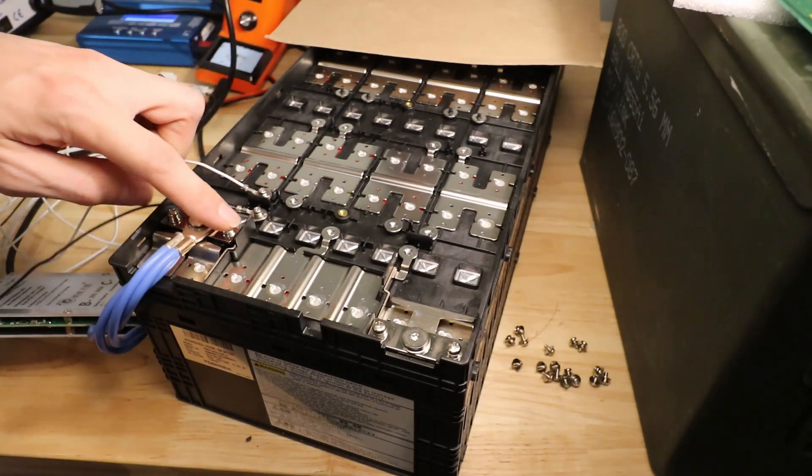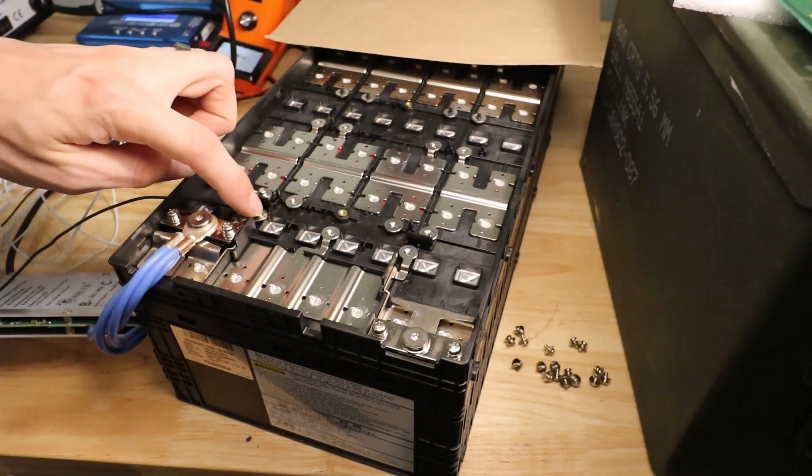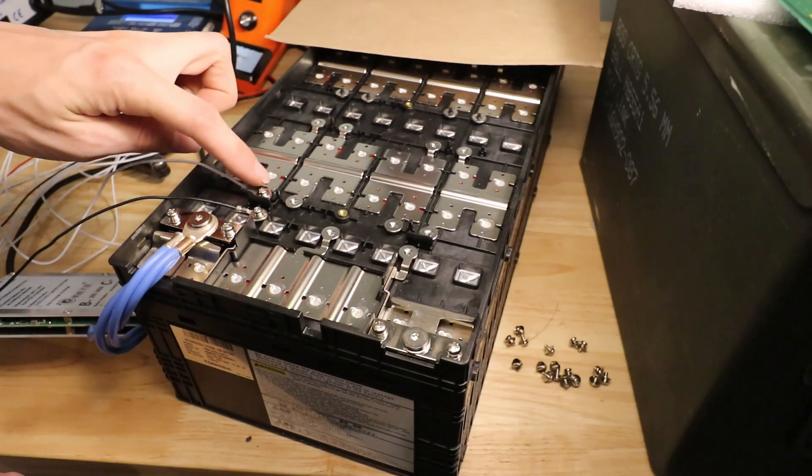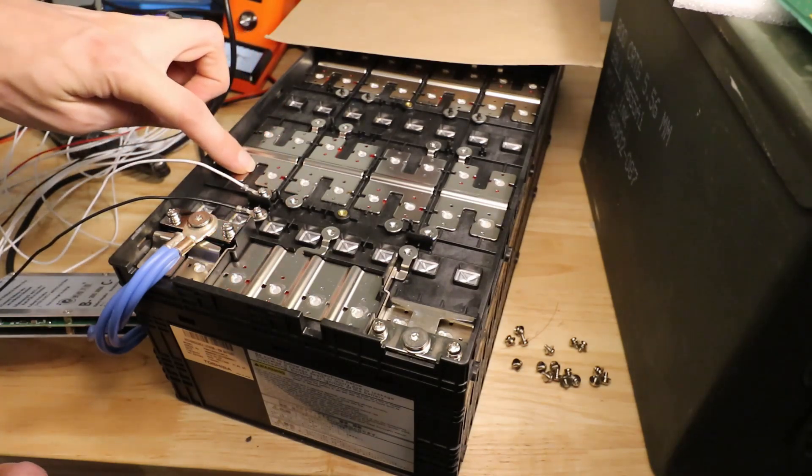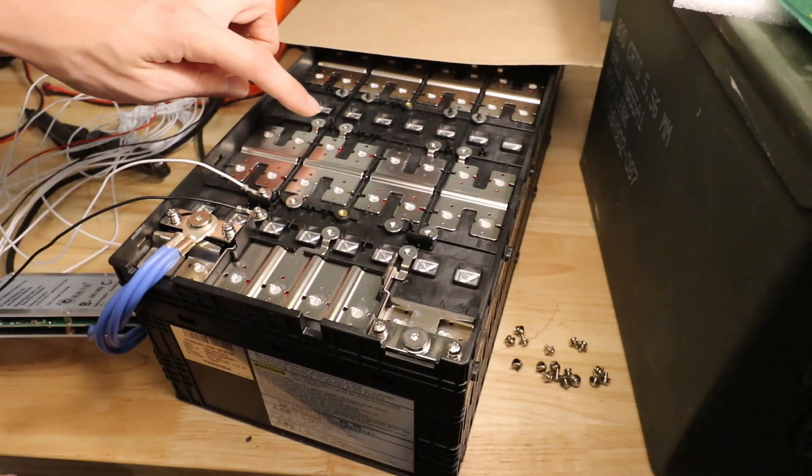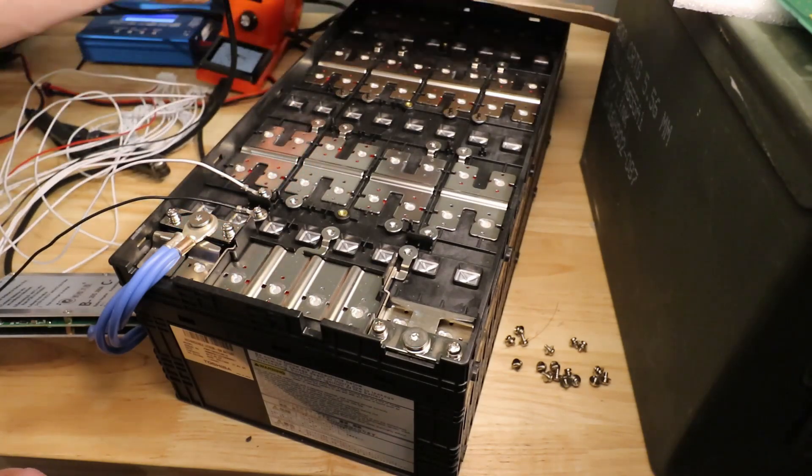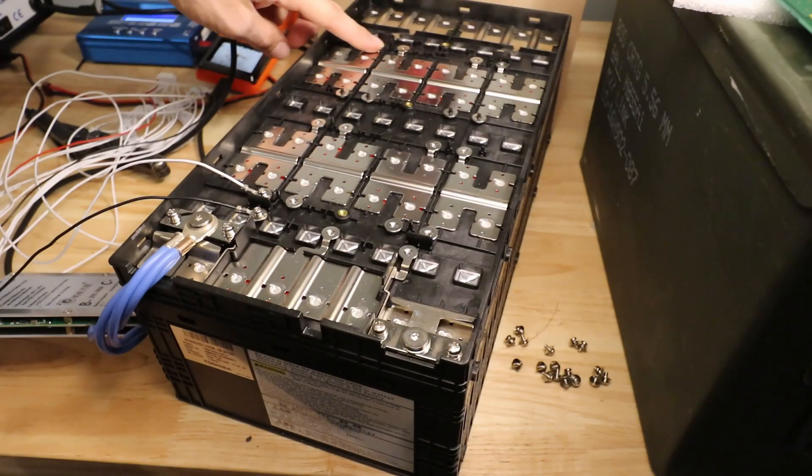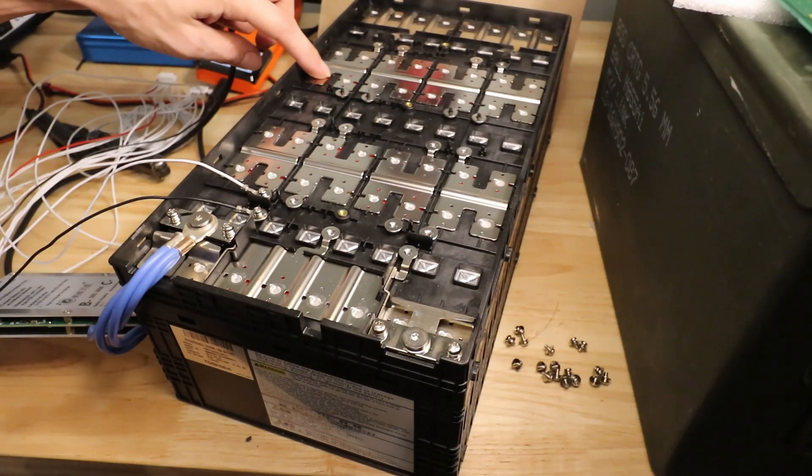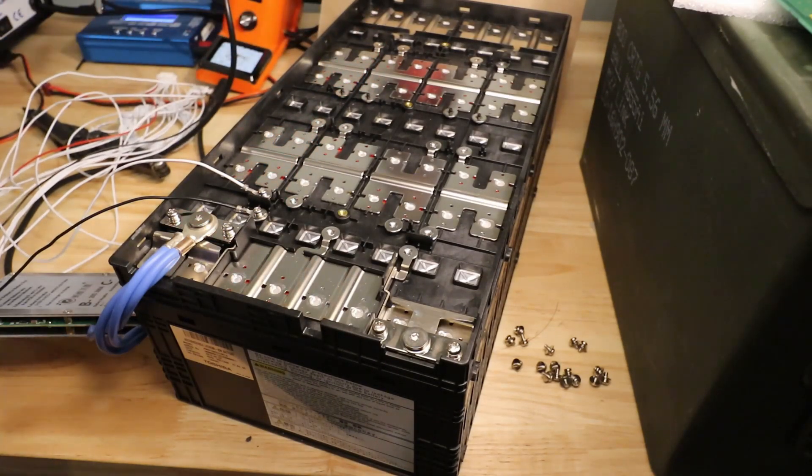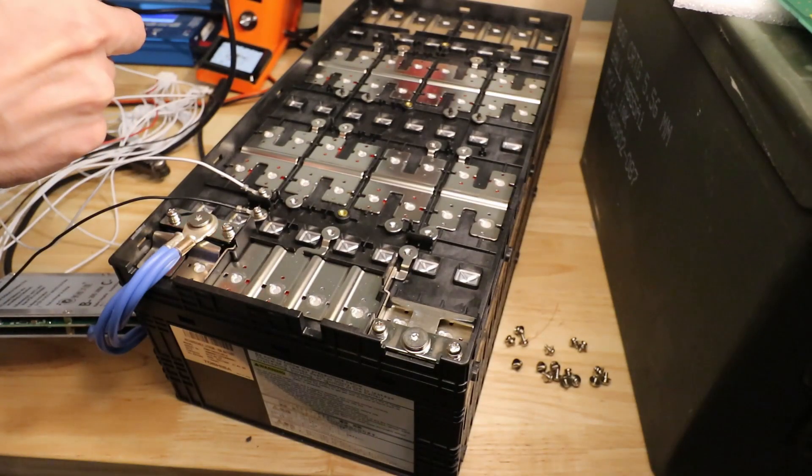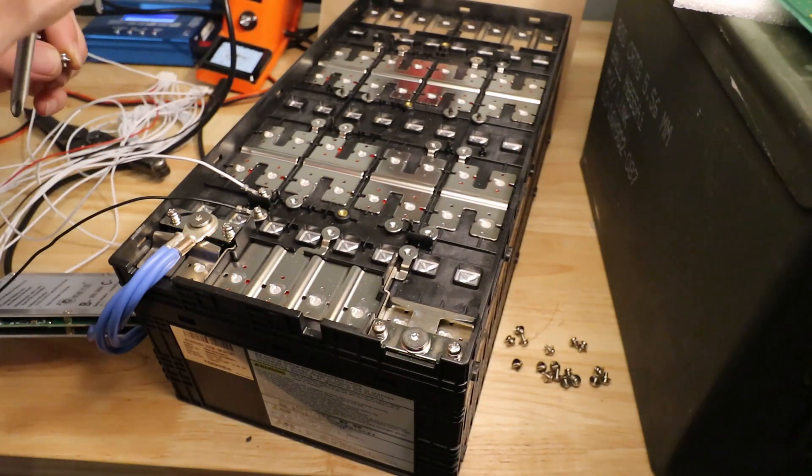So you've got main negative here, which is also this little tab. And then you've got first positive. And then you will skip this because it's the same tab and come over to here, which will give you second positive. So that's what I'm going for next. It's important to understand how the battery's built before you just start connecting things.